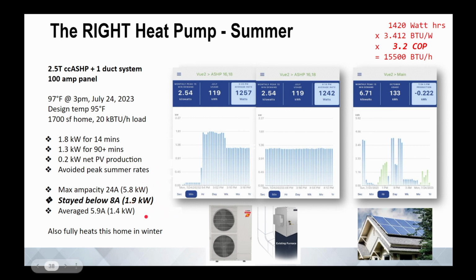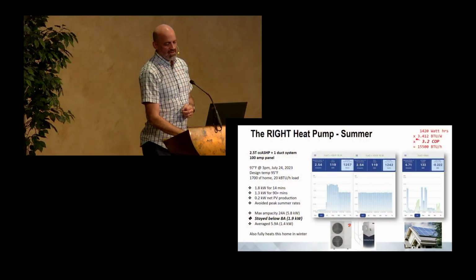Here's the kicker. How much power do you need? It's rated for 24 amps, 30 amp circuit, rated for 24 amps ampacity. It's 5 kW. It stayed below 8 amps, and it averaged under 6 amps for that hour and a half. So what's going on here? We're past the design conditions. We sized the system for the design conditions, but we're operating well below those. What's really happening? Any guesses? This is for the, well, sorry, Martin, I'm holding the questions to the end. We'll come back to it. What I really love is that we're still operating at 320% efficient.